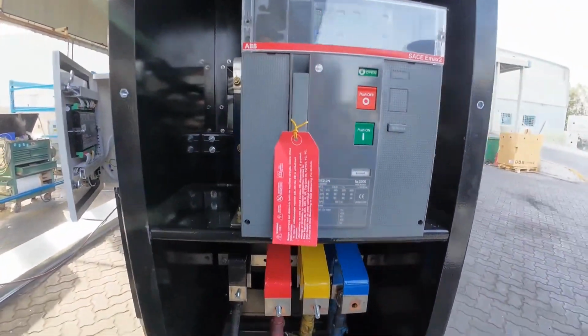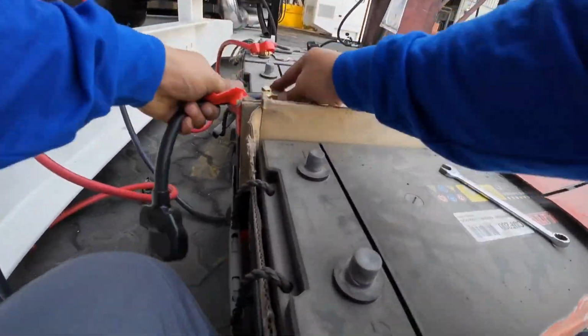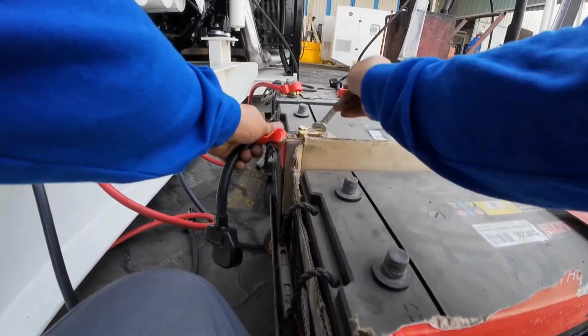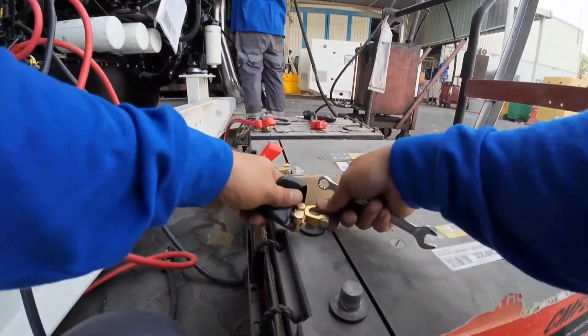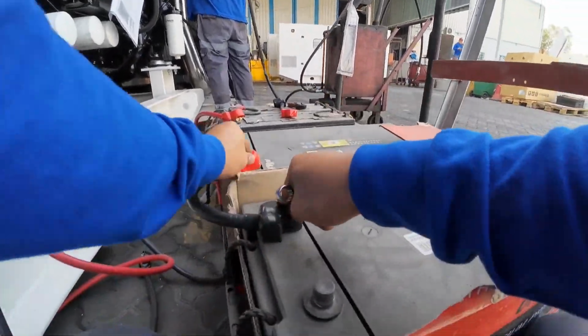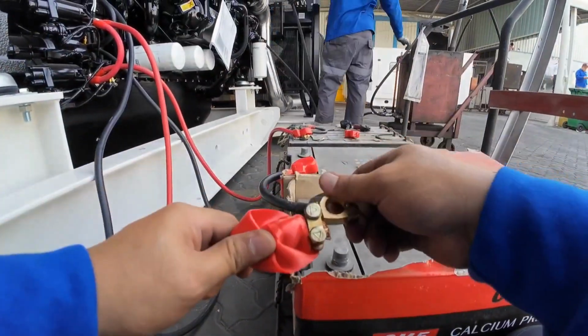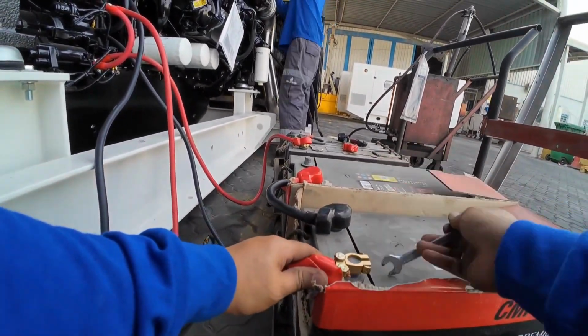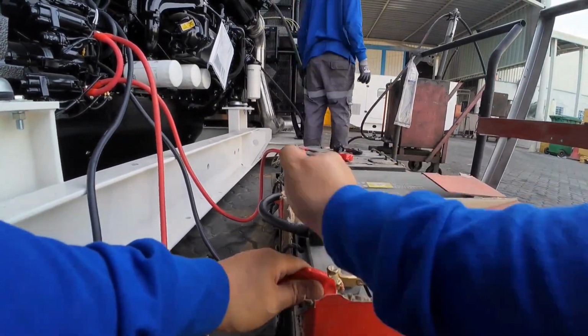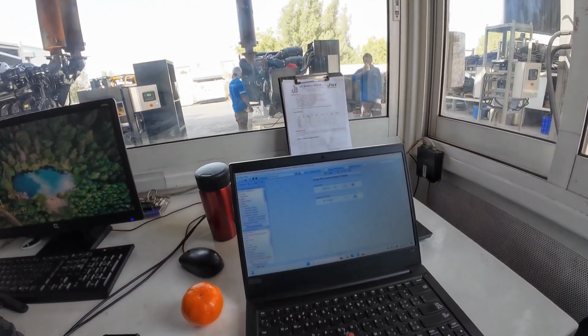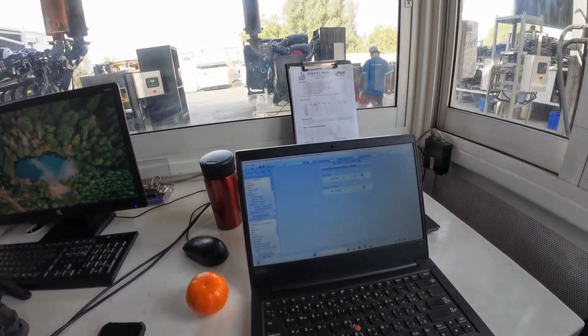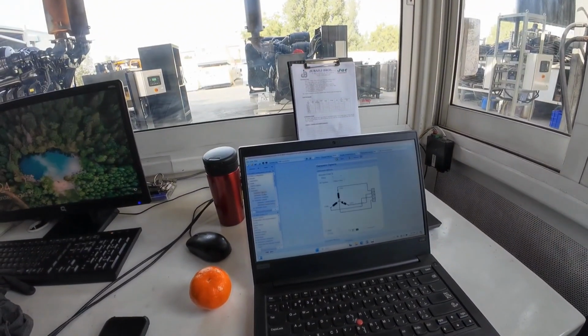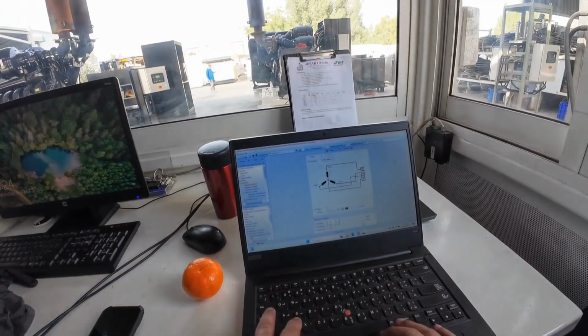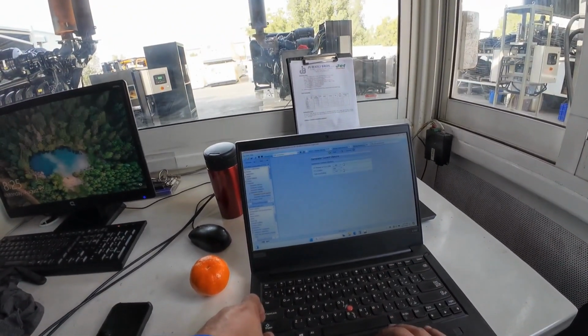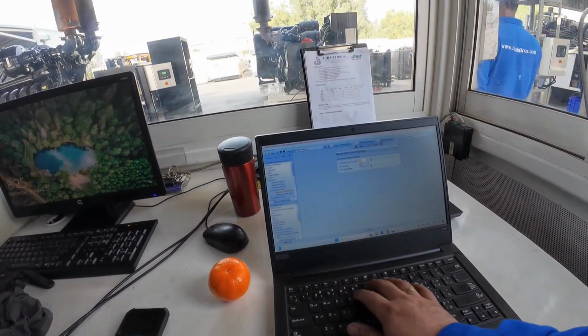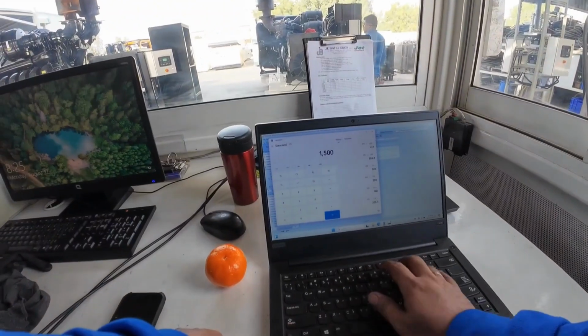Here we're checking our breaker and connecting the battery so we're ready for configurations. This one is 24 volts, so it's a series parallel connection. I'm also preparing the configurations for our 1500 kVA settings and proper configuration for this generator.